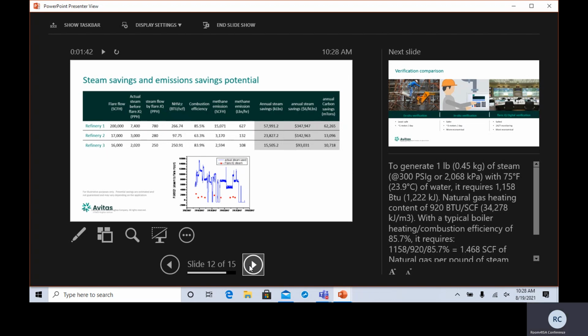If you go to a powerhouse engineer at a refinery and say, hey, if you had more steam available to you, could you use it? Most of them say yes. What we're doing is we're reducing the load on the boiler system by 15 million pounds. And if you put a dollar figure to that, we put $6 per 1,000 pounds of steam as the cost to generate and transmit that.